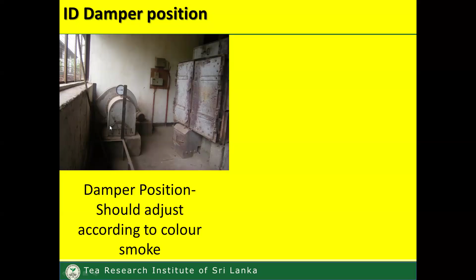It should be adjusted according to the color of the smoke which comes out of the chimney, right? You can see it is more like white color smoke, right? Then you have to adjust the damper position until you get the proper condition.